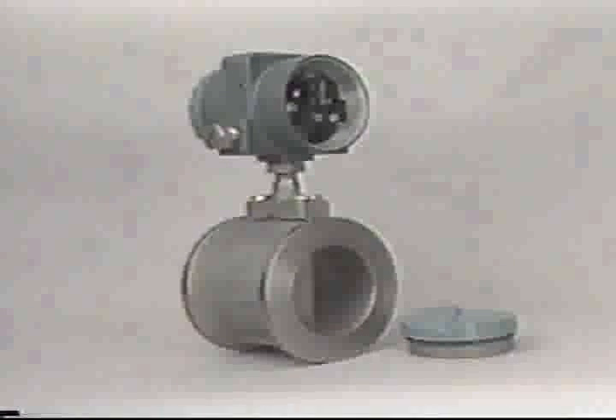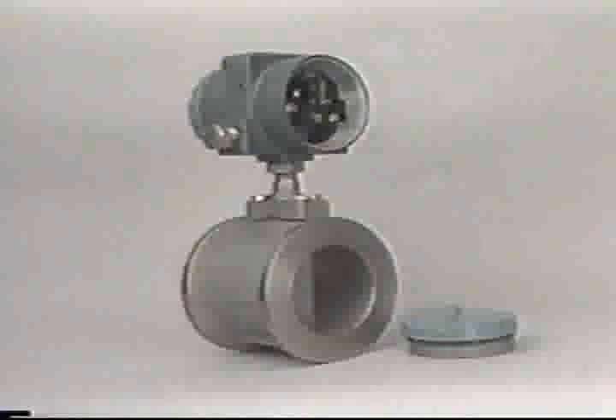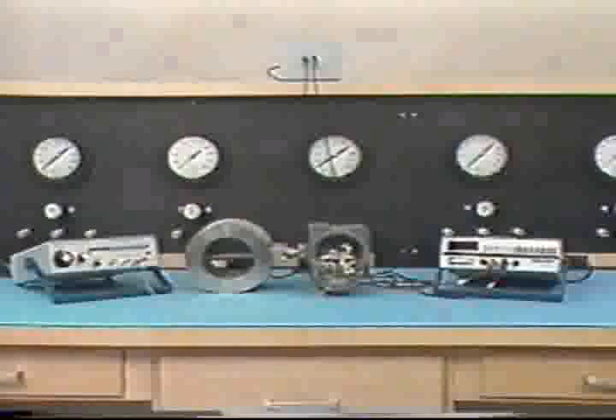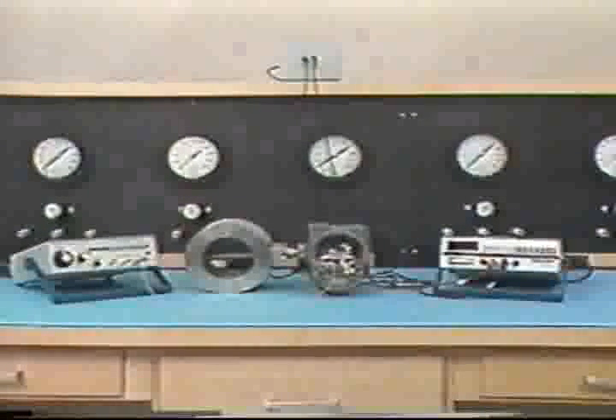A vortex shedding flow meter can also be used to measure fluid flow. In this segment, we'll see how to calibrate this instrument. It requires a special input standard. But first, let's look a little more closely at how a vortex shedding flow meter works.